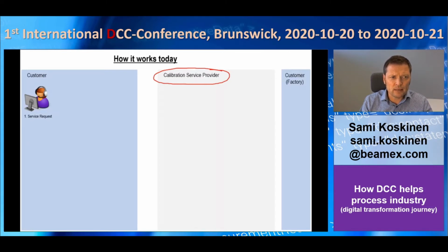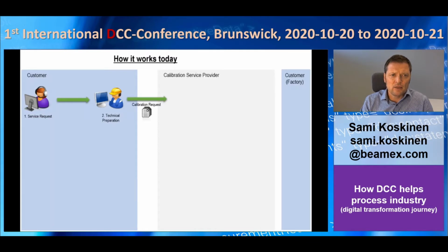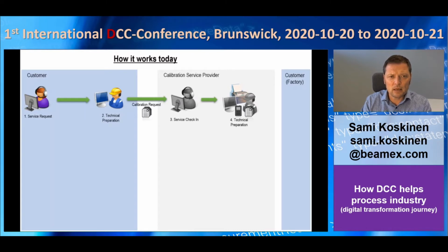First of all, the customer raises a service request, and then it requires a technical preparation. Once technical preparation is done, they will pass the service request to their calibration service provider, whether it's on paper or a PDF or email. However, it's pretty much a manual process here. And then the service provider will check the service request into their own systems. Then it goes to the next step, a technical preparation on the calibration service provider side. And here they need to make sure that they have all the required tools available. They will reserve the resources for the calibration work itself, make sure that they have appropriate reference standards available, and so on and so on.